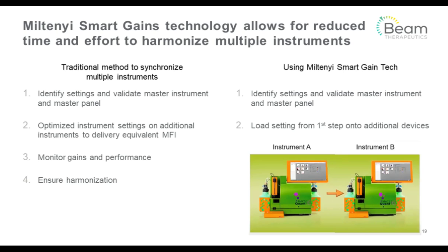Another key piece of software that Miltenyi has that Beam is big fans of is their SmartGain technology, which actually allows for reduced time and effort to harmonize multiple instruments, whether it's within your lab, within groups, or within manufacturing sites across the world. Now on the left, I've listed traditional methods that usually you have to take to synchronize multiple instruments, whether it's starting out with identifying your master settings, validating those settings on your master instrument panel.